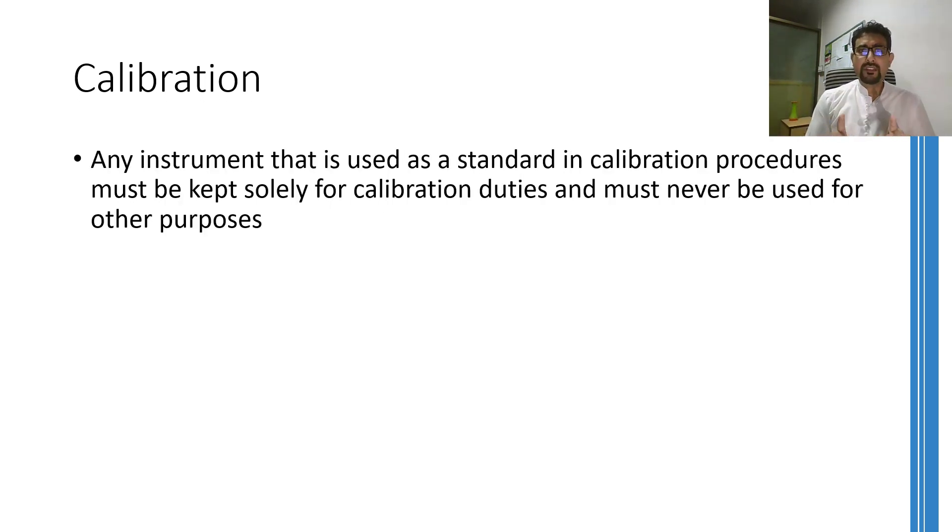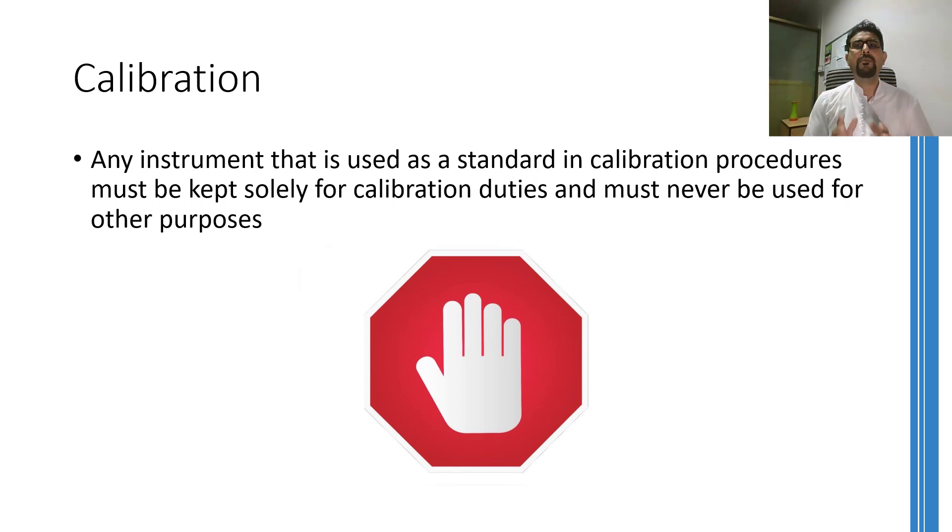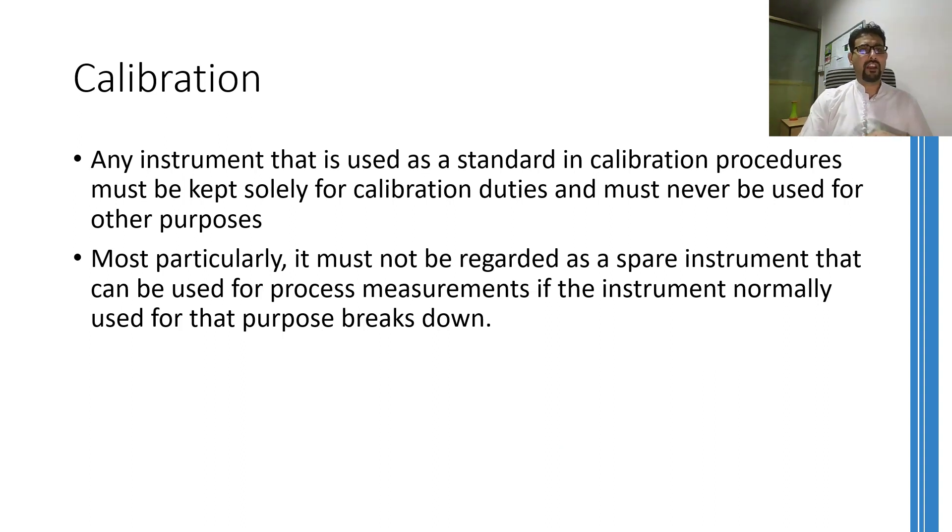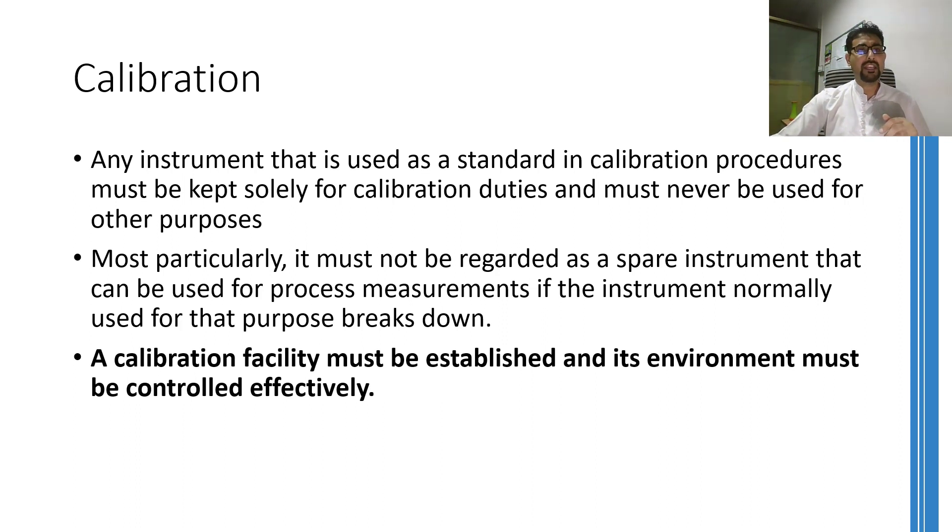Please note one thing that whatever instrument is being used for calibration procedures must never be used for any other purpose because if you are going to use that calibration instrument for any other purpose, then the accuracy and integrity of that instrument may be compromised. Therefore, calibration equipment must never be considered as a spare part or a spare instrument and must never be replaced even for a tiny amount of time for any instrument that is being used in the factory floor. Moreover, depending on the size of the factory or the industrial setup, a calibration facility must be established inside the industrial setup and its environment must be controlled effectively so that whenever there is a need for calibration, the first lab or the first facility any instrument must visit should be inside the industrial premises.